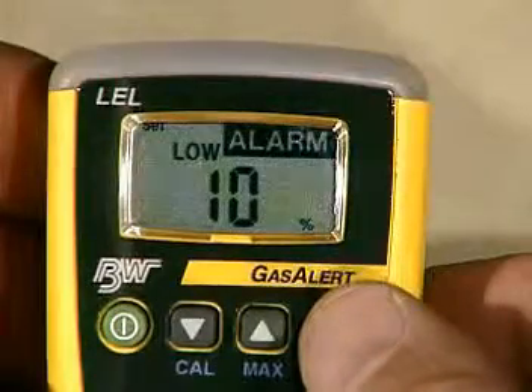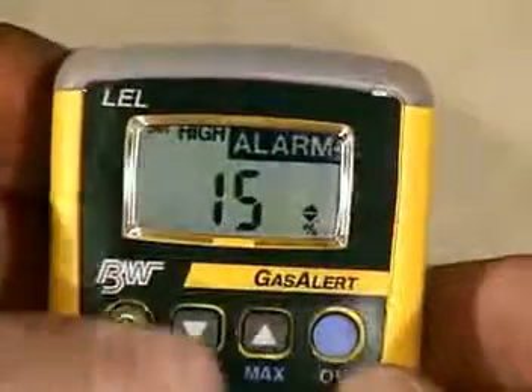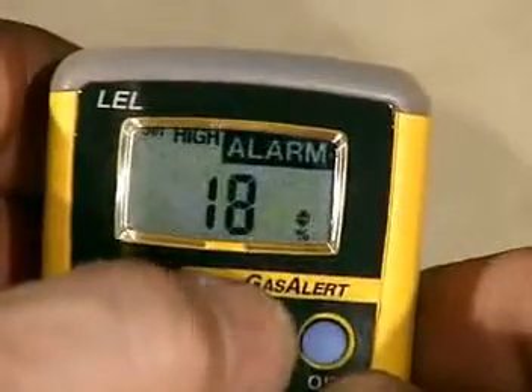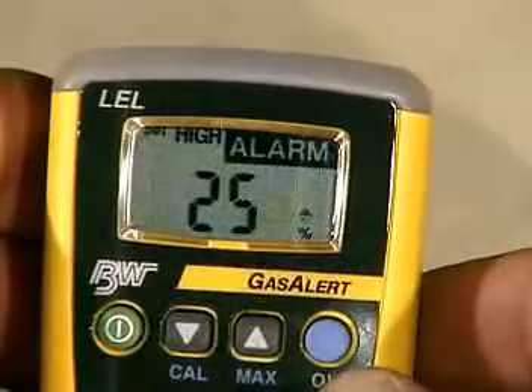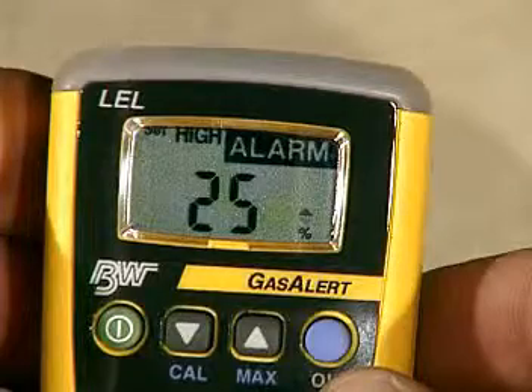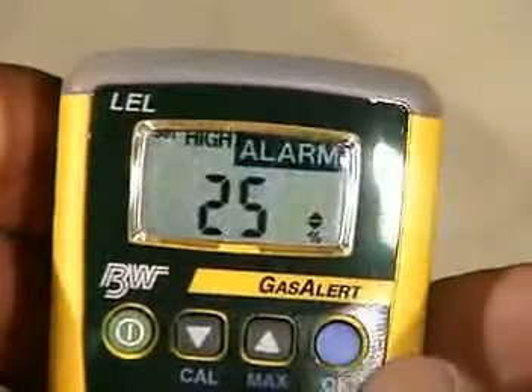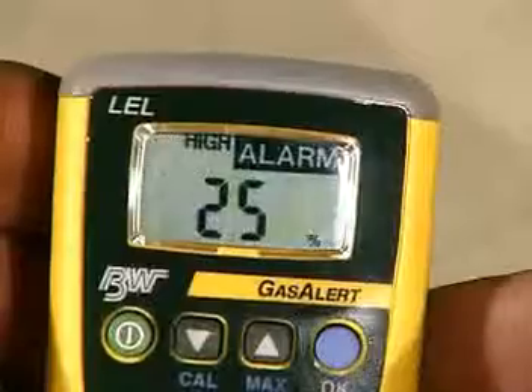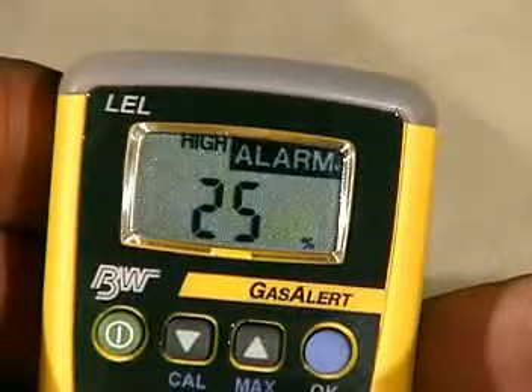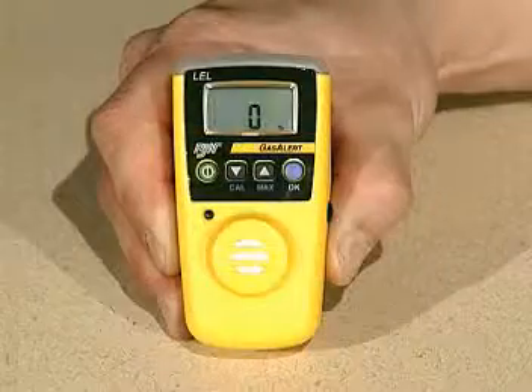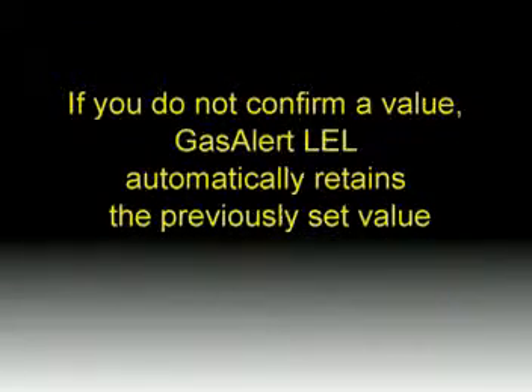The display will then read Set High Alarm and will display the current high alarm set point. Press the up or down arrow buttons until the display shows the desired value and then press OK to save the new set point. The detector beeps 4 times before returning to normal operation. If you do not confirm a value by pressing OK, GasAlert-LEL will automatically retain the previously set values.